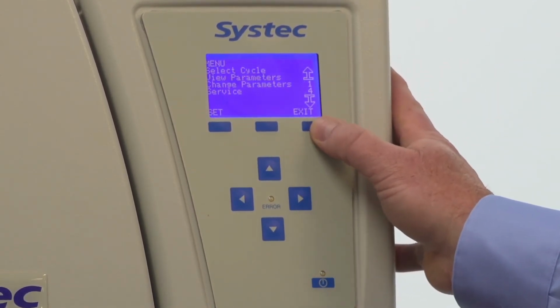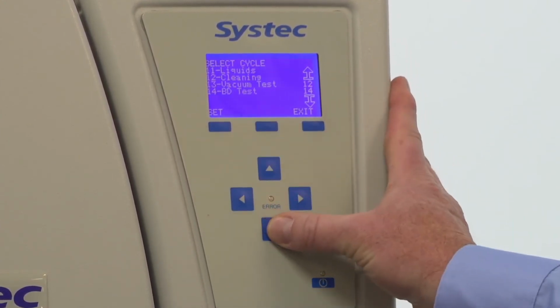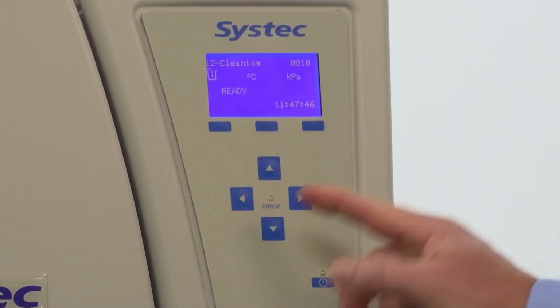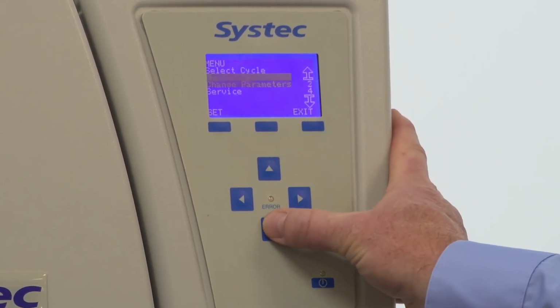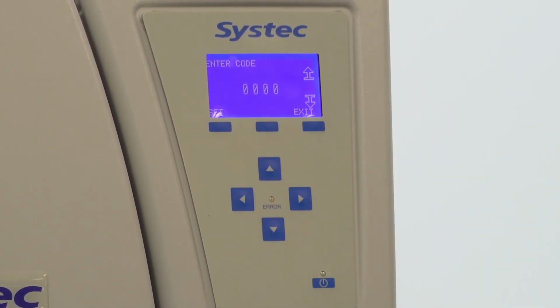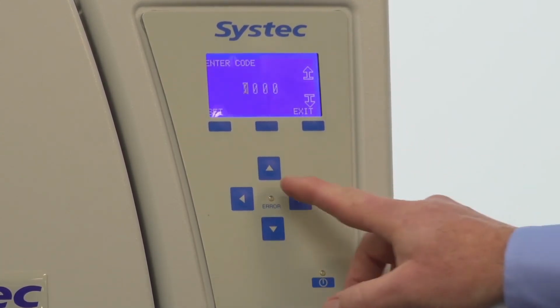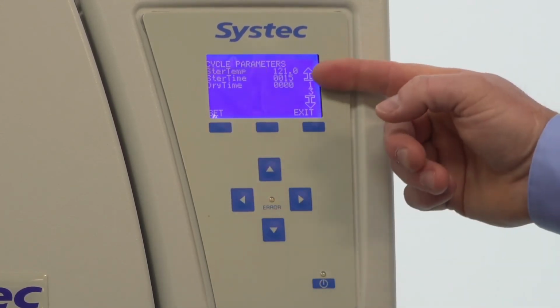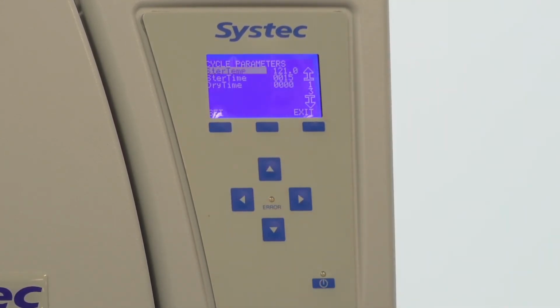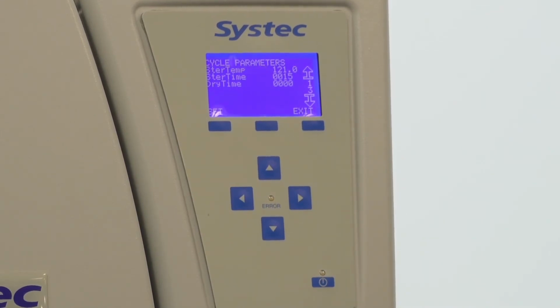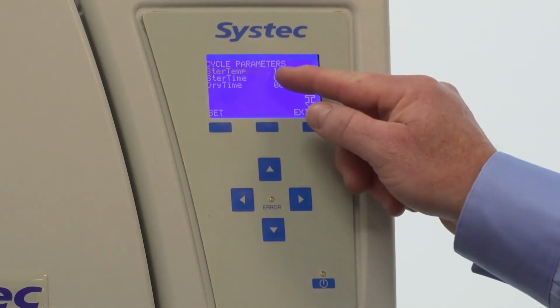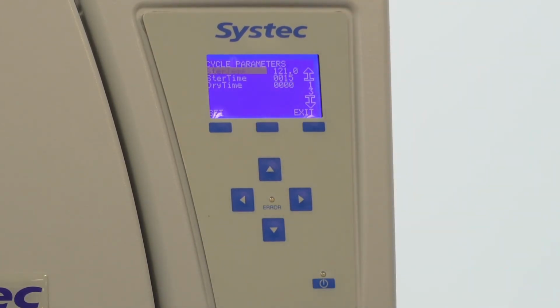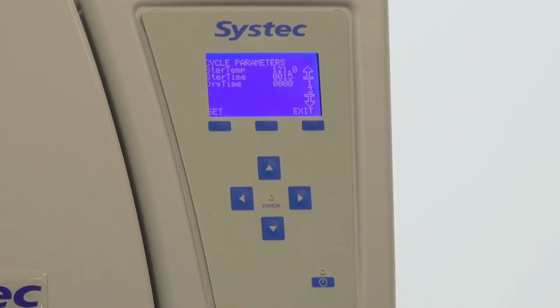The programming on this, once we select a cycle, is simply to go into the cycle and hit set, and if I want to program it, I just hit change parameters. It's going to ask me for a user code in order to do that. I have 3 different user codes. 1000 is the most basic, so if I enter that, it allows me to change 3 parameters. I can change the drying time, the sterilization temperature, and the duration of the sterilization time. The more parameters that I want to access, I can enter different codes that give me more access to the different parameters for the instrument.